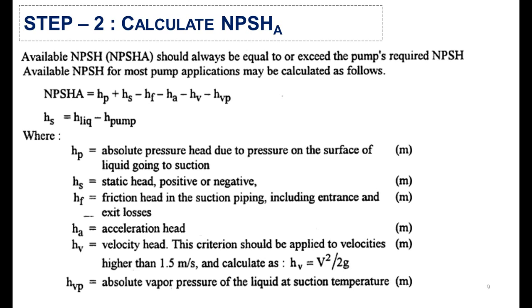In the second step, you will calculate the net positive suction head available. Here is the formula: Hp is the absolute pressure head due to pressure on the surface of the liquid going to suction; Hs is the static head, positive or negative; Hf is the friction head in the suction piping including entrance and exit losses; Ha is the acceleration head; Hv is the velocity head; and Hvp is the absolute vapor pressure of the liquid.